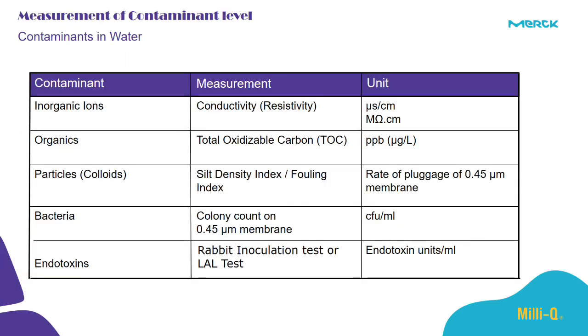Several measurements are used to detect the level of contamination in water. In laboratories, we focus on five types of them. The first one is inorganic ions. The measurement for it is conductivity or resistivity, and the units are microsiemens per centimeter for conductivity and megaohm-centimeter for resistivity. Organics are measured as total oxidizable carbon, TOC, in parts per billion or micrograms per liter. Particulates or colloids are measured by silt density index, or fouling index, with units based on the rate of blockage of a 0.45 micron membrane. Bacteria are measured by colony count on a 0.45 micron membrane, in colony forming units per milliliter. For endotoxins, the measurement is the Rabbit Inoculation test, or LAL test, in endotoxin units per milliliter.